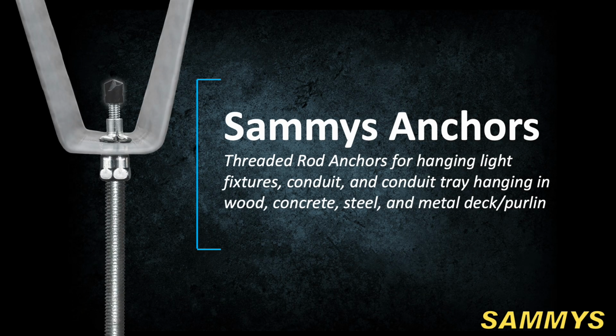Now let's move into Sammys, which many of you already know from the field. Sammys anchors are our threaded rod anchoring system for hanging light fixtures, conduit, cable tray, and other MEP components. We offer versions to be used for wood, concrete, steel, and metal deck or purlins.